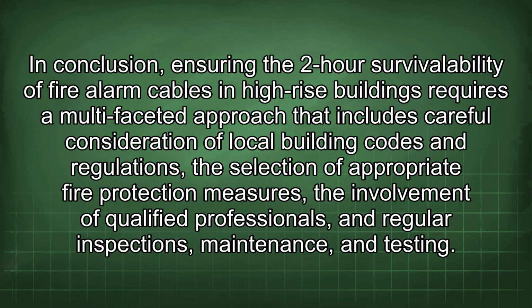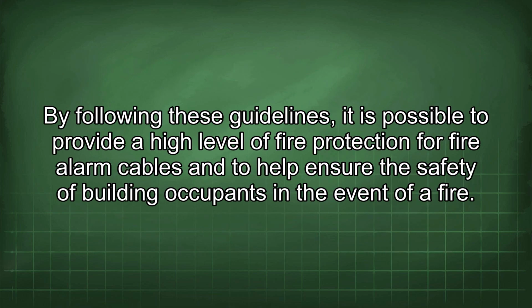In conclusion, ensuring the 2-hour survivability of fire alarm cables in high-rise buildings requires a multifaceted approach that includes careful consideration of local building codes and regulations, the selection of appropriate fire protection measures, the involvement of qualified professionals, and regular inspections, maintenance, and testing. By following these guidelines, it is possible to provide a high level of fire protection for fire alarm cables and to help ensure the safety of building occupants in the event of fire.